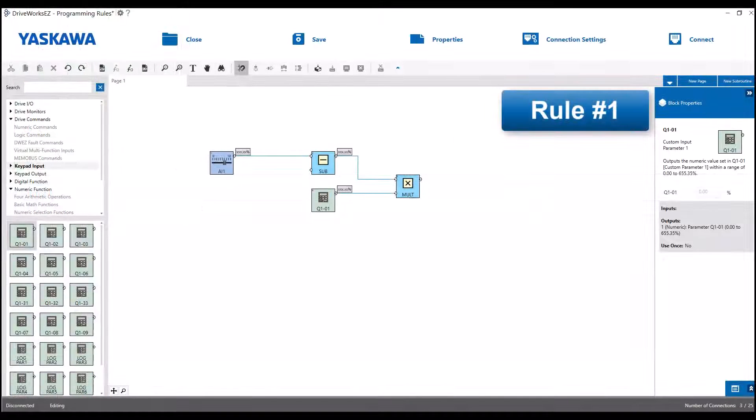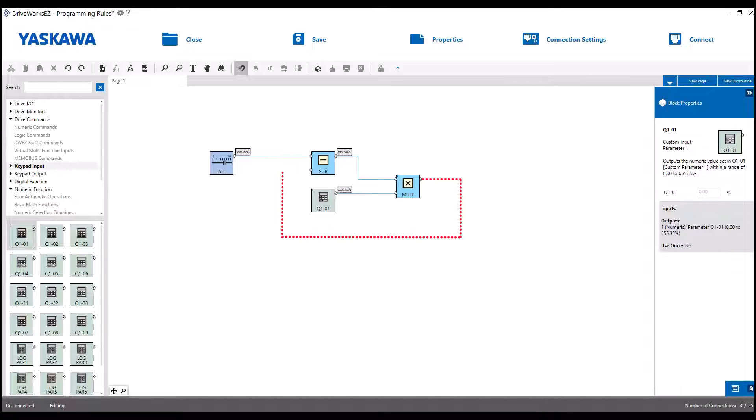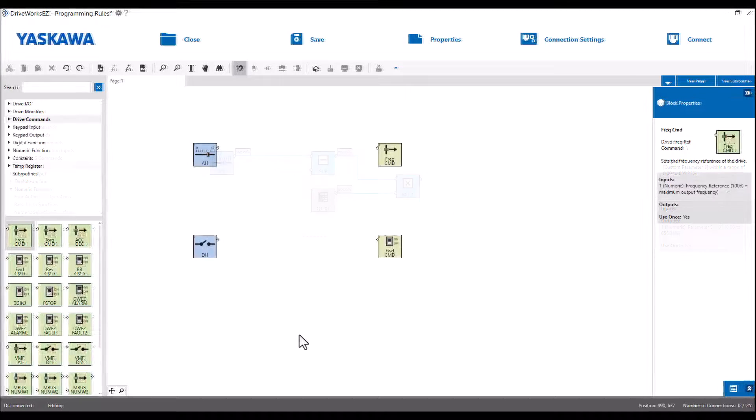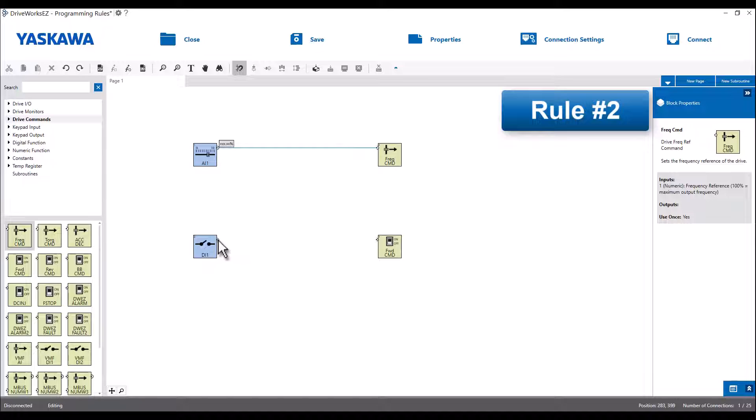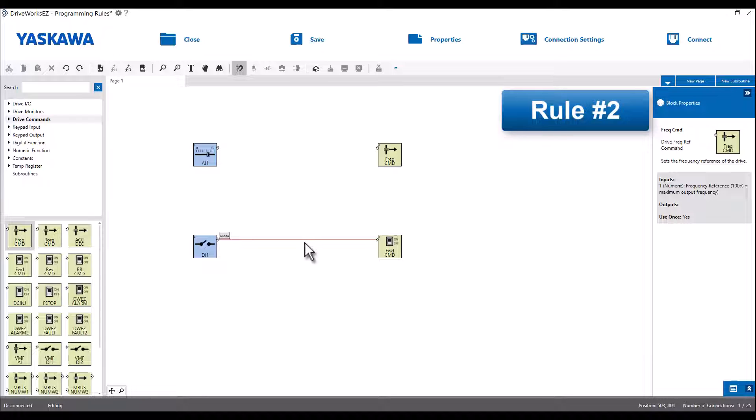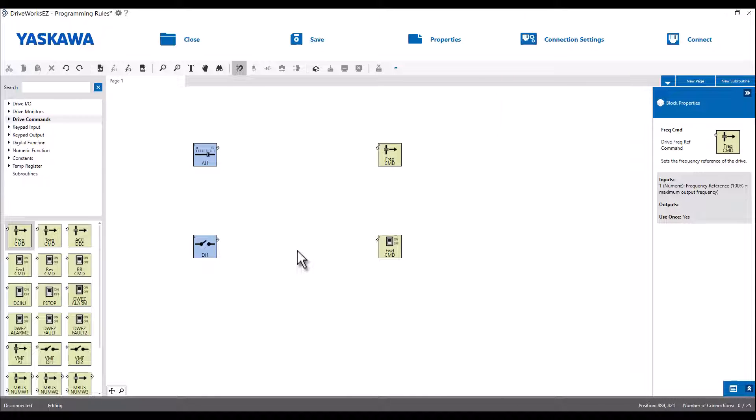The first rule is the output of one block cannot be connected to the input of a block prior in the sequence. So we can't take the output of this block and connect it back to the input of a block earlier in that same rung. Another rule is that numeric outputs can only be connected to numeric inputs and the same for logic outputs and inputs. You can't mix and match them because the program actually won't even let you do that. You'll see that you won't be able to make a connection between the two before you even get a chance to compile.